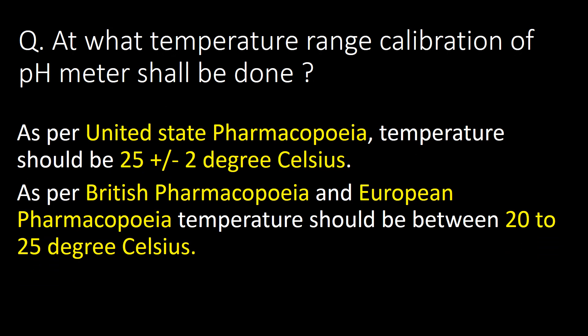At what temperature range shall calibration of a pH meter be done? As per USP, that is the United States Pharmacopoeia, temperature should be 25 plus or minus 2 degrees Celsius. Whereas as per the British Pharmacopoeia and European Pharmacopoeia, temperature should be between 20 to 25 degrees Celsius.